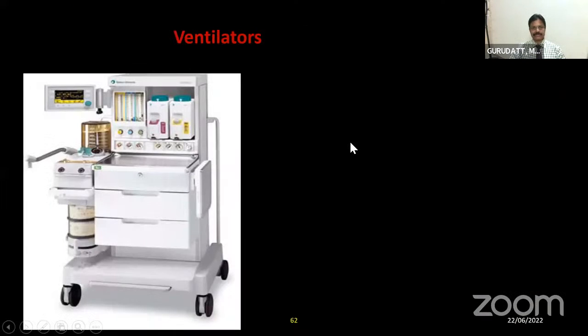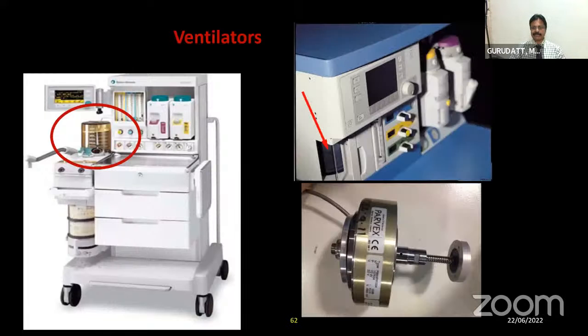And again, I was discussing with you the difference of ventilators in the case of GE and Draeger machines. In Draeger, we have piston-driven ventilators. They are electrically driven. In the case of GE machines, we have bellows ventilators and double circuit ventilators. You require a driving gas of oxygen here, but in the Draeger you don't require a driving gas because they are electrically operated. So that is one of the disadvantages with the bellows ventilators.